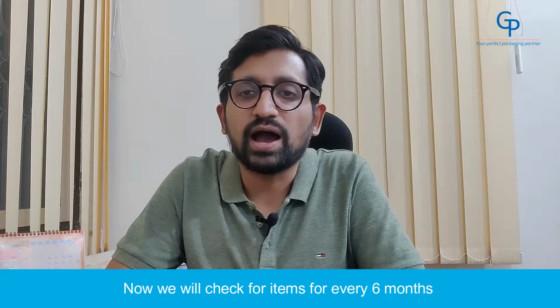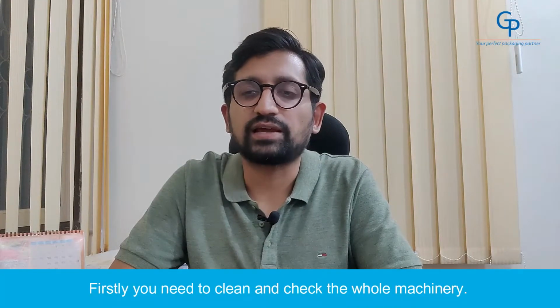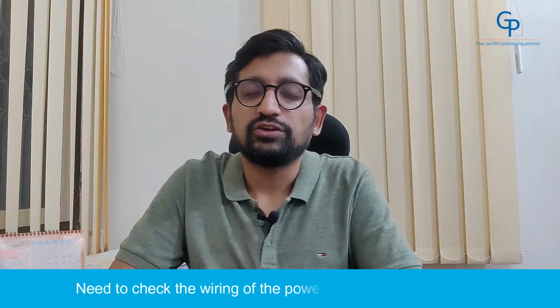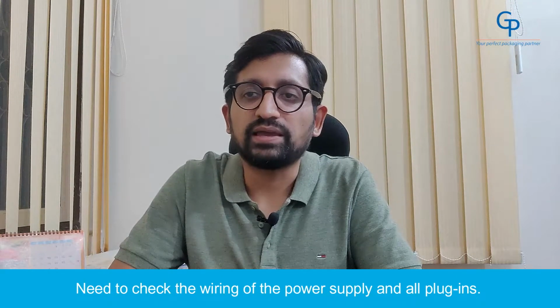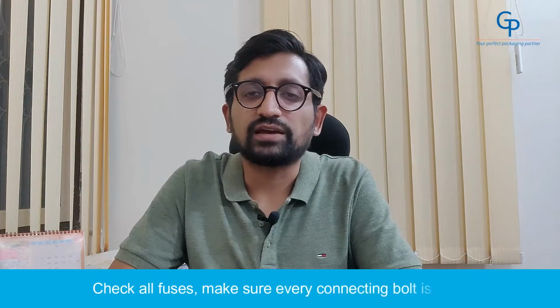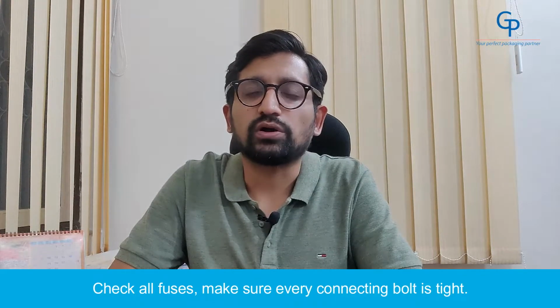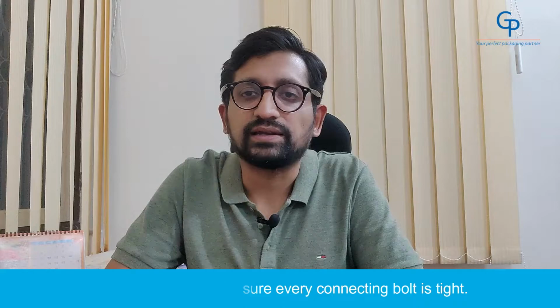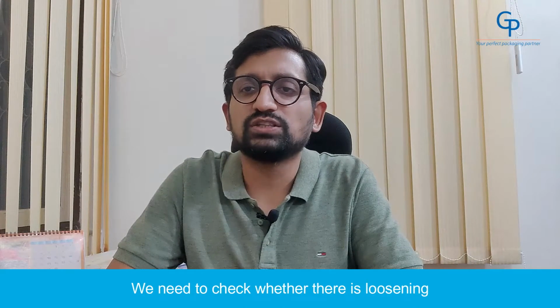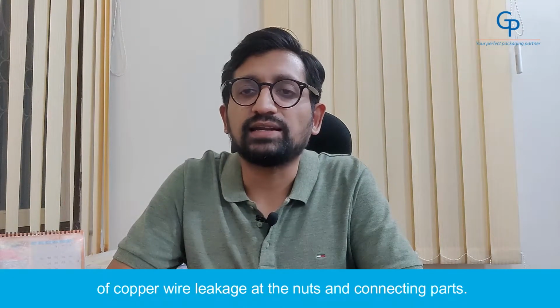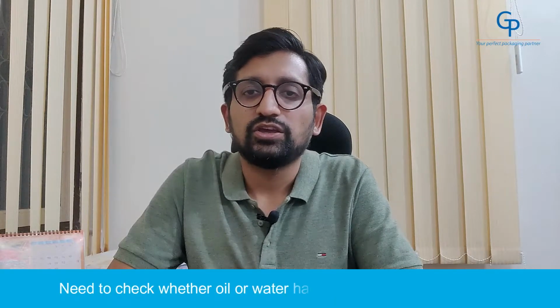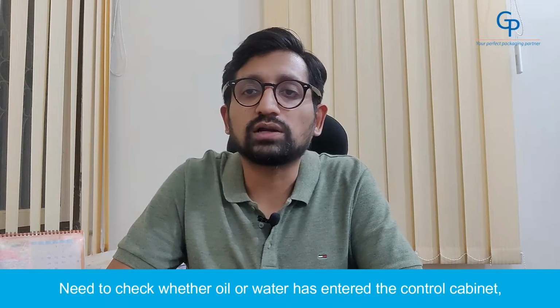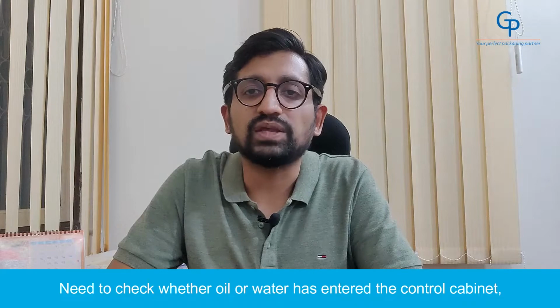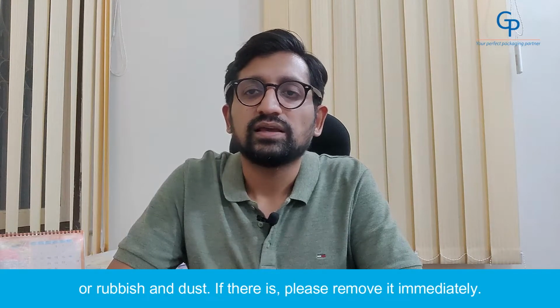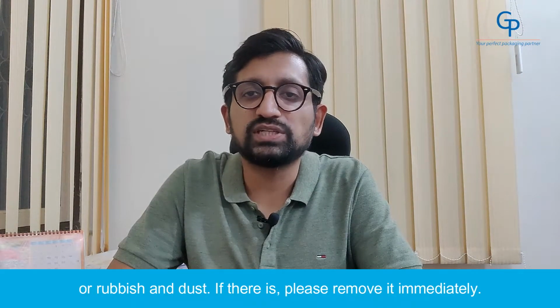Now, we will check for items for every 6 months. Firstly, you need to clean and check the whole machinery. You need to check the wiring of the power supply and all plugins. Check all fuses. Make sure every connecting bolt is tight. You need to check whether there is loosening or copper wire leakage at nuts and connecting parts. You need to check whether oil or water has entered the control cabinet or rubbish and dust. If there is, please remove it immediately.